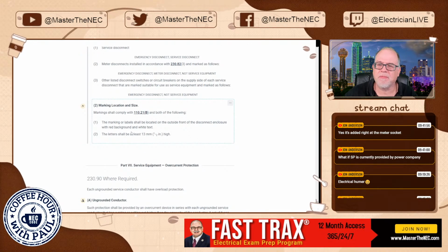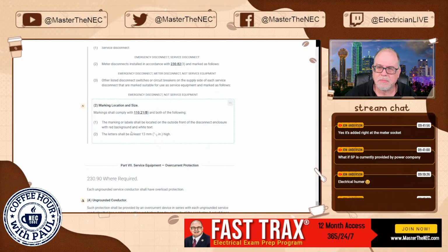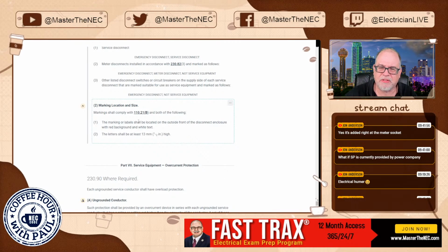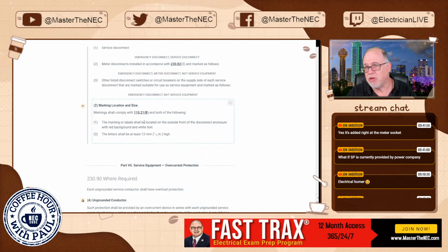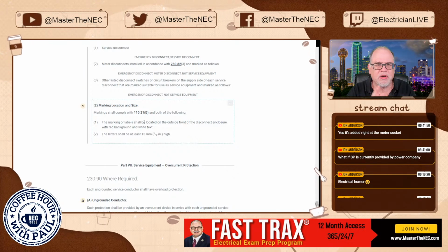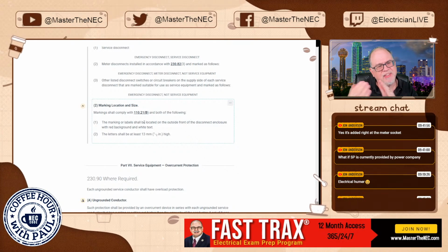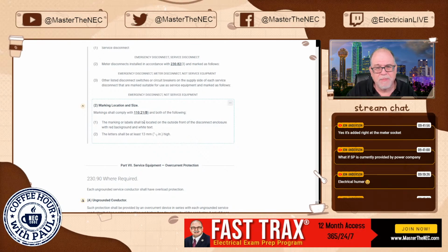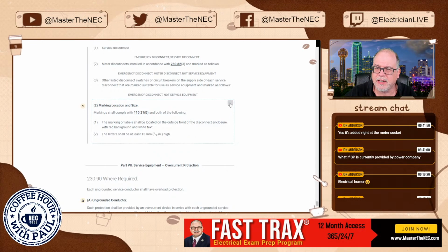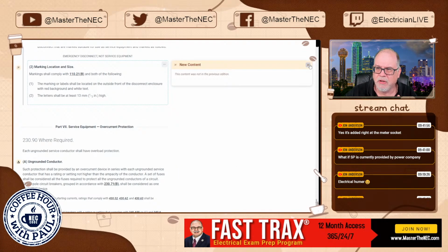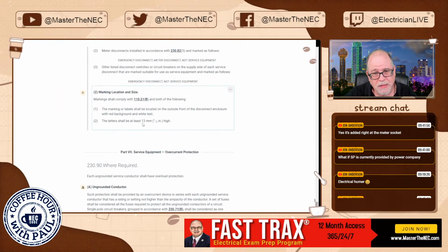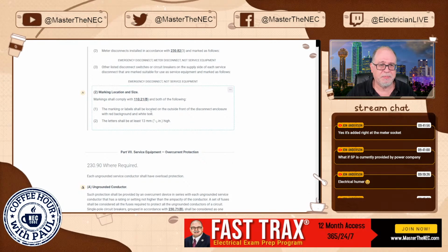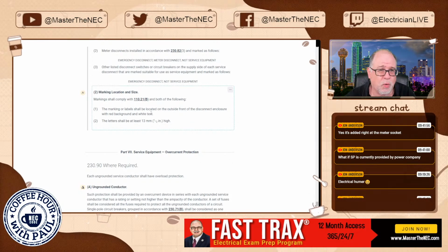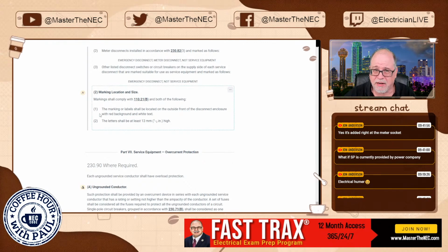Marking locations, same as you had before. It has to be on the outside front of the disconnect enclosure. Jay, the Basement King, and I have talked about that before, about whether it's inside the cover or outside of the cover. The code is being very clear here. And you'll notice here when I click View Changes, you're not going to see anything. See, it's not here. So it's not that this is all new, but it wasn't as descriptive as it is now in the 2023. And I'm all about clarity, my friends.